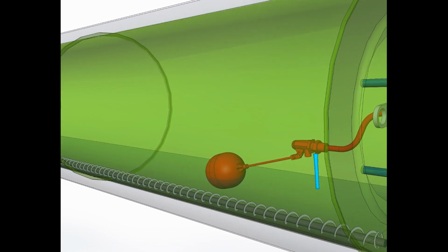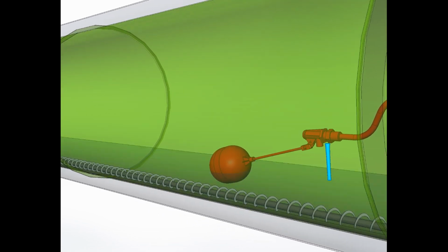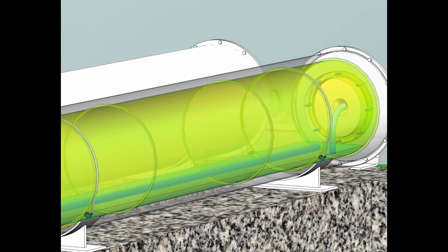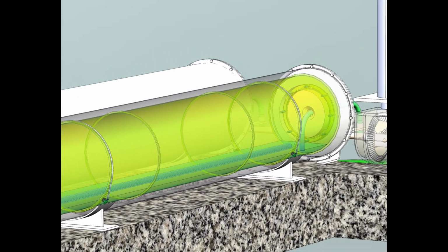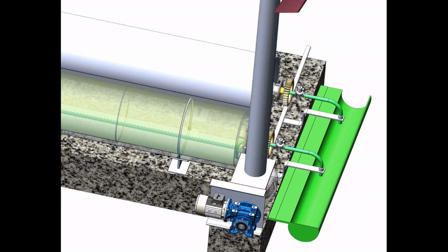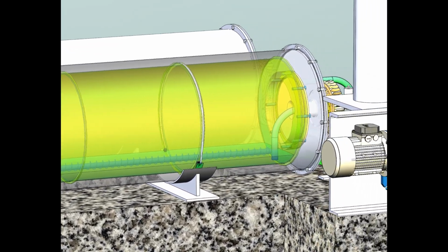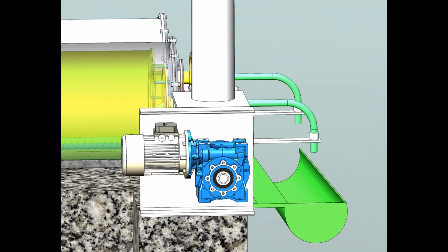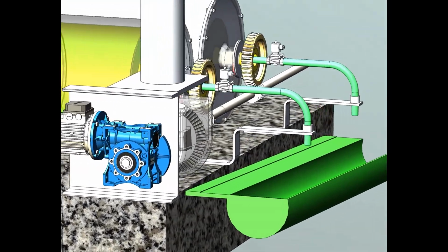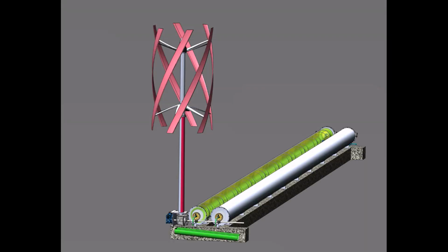The discharge of concentrated brine is carried out by periodically opening a solenoid valve after the target salinity level is reached. The brine concentrate is expelled under increased pressure in the drum through a stationary pipe, one end of which is submerged below the brine concentrate level in the drum, while the other end drains the concentrate into an inclined trough for transfer to the evaporation pond.